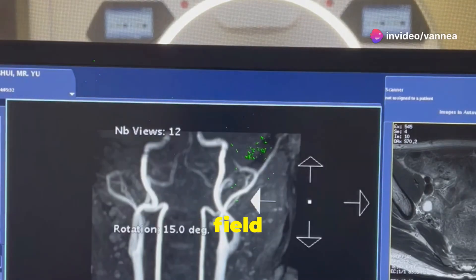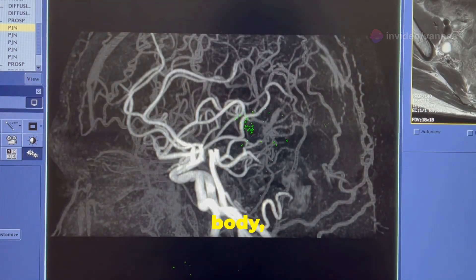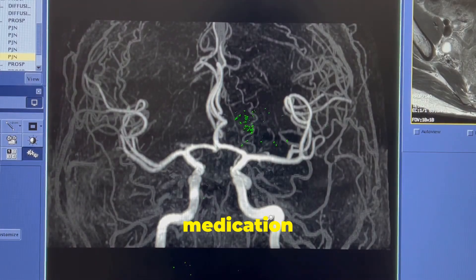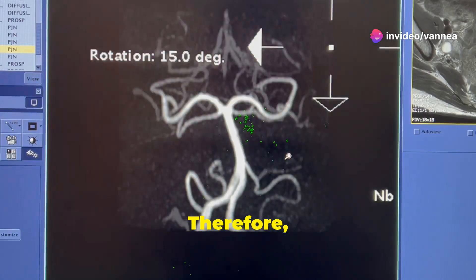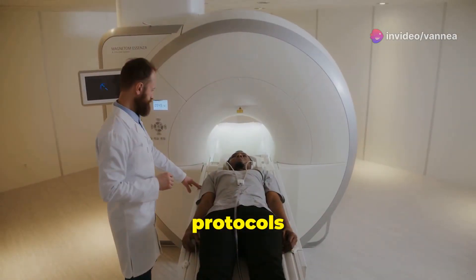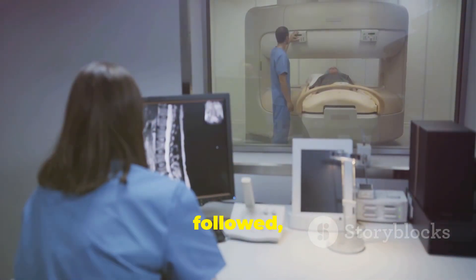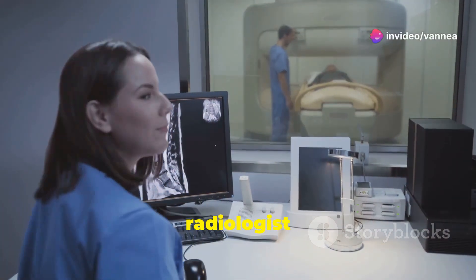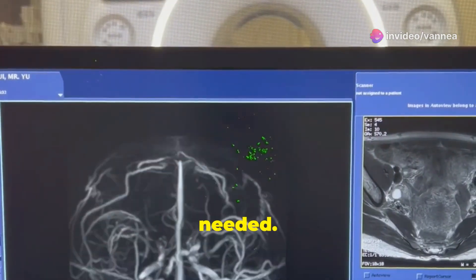The powerful magnetic field of the MR system will pull on any ferromagnetic object in or on the patient's body, such as a medical implant — for example, certain aneurysm clips, medication pumps and so on. Therefore, all MRI facilities have comprehensive screening procedures and protocols they use to identify any potential hazards. When carefully followed, these steps ensure that the MRI technologist and radiologist know about the presence of any metallic objects so they can take precautions as needed.